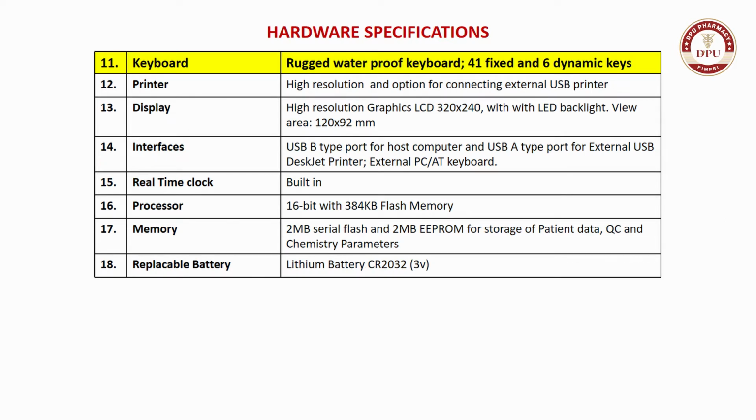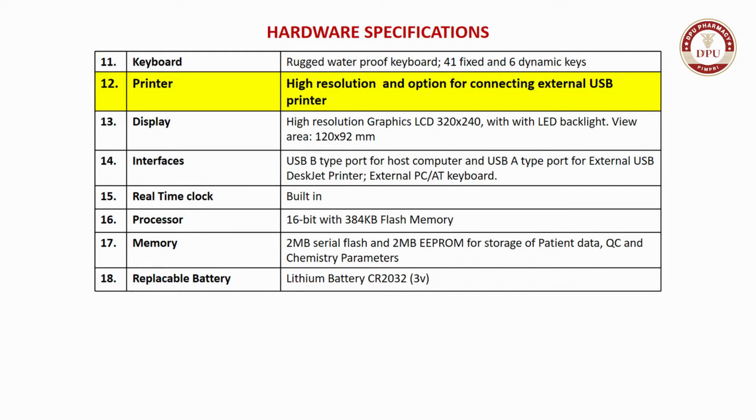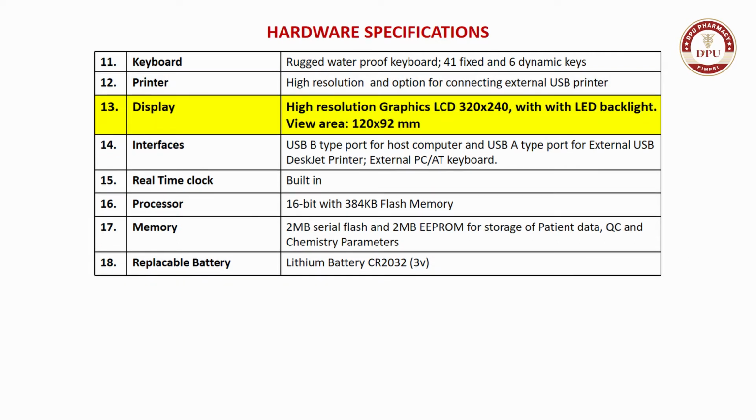The keyboard of the device is a rugged waterproof keyboard, and it has 41 fixed and 6 dynamic keys. The printer is also present in the device. It is high resolution and an option for connecting an external USB printer is also there. Now the display is a high resolution graphics LCD, 320 by 240, with LED backlight, and the view area of the screen is 120 by 92 mm.